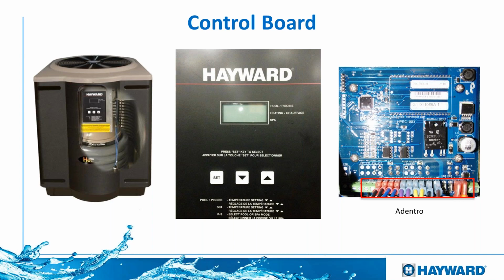Then we have this little empty spot that you see here, guys. This is a connection only for units that also cool your water. So for heat cool units, you will have a reversing valve and it will be connected right there. If you don't have a heat cool unit, then pretty much that spot is going to be empty since we have no reversing valve to energize. Then after that, we have two more wires at the end. These are the 24 volts that come from the transformer to the board to energize the board or the controller.